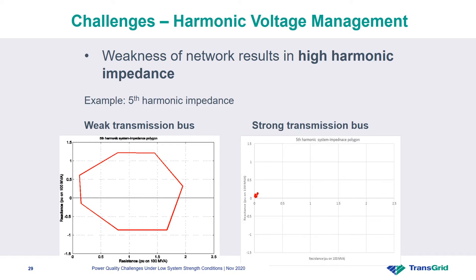We generally understand weak networks are inherently characterized by high network impedance. It holds true for harmonic impedances as well. Harmonic impedances are high at weak network locations. You can see a comparison of fifth harmonic impedance at a weak and strong network location. The graph shows fifth harmonic impedance as a polygon in per unit. You can see that the impedance at the strong transmission bus is a fraction of the impedance at the weak transmission bus.